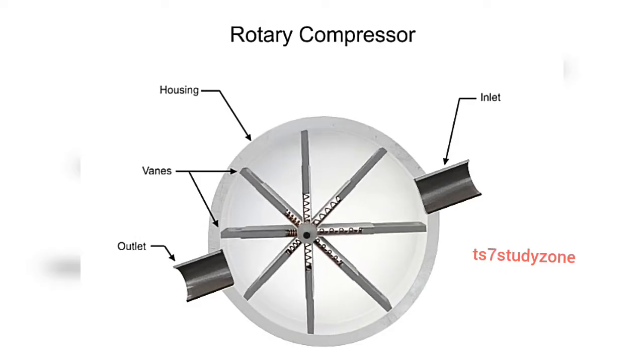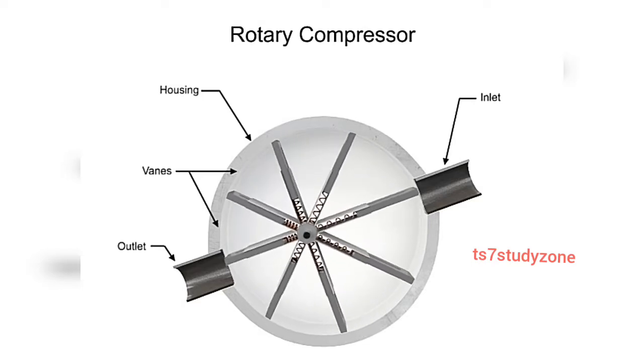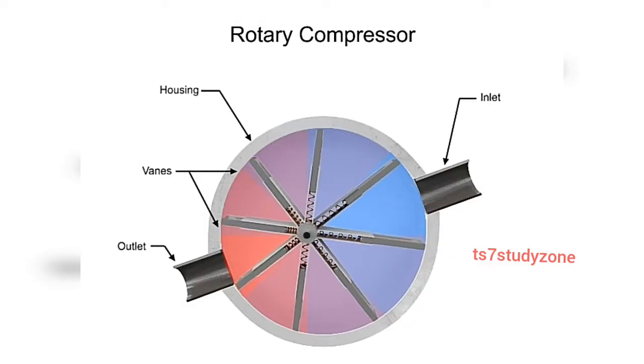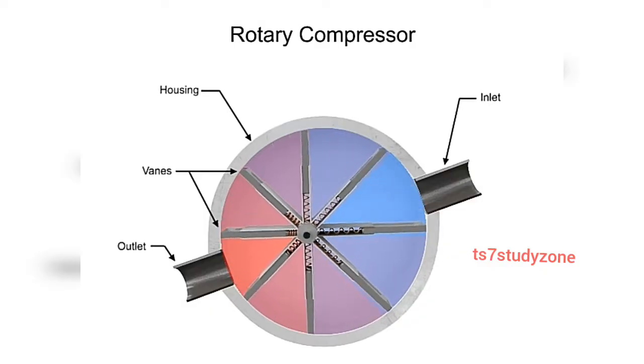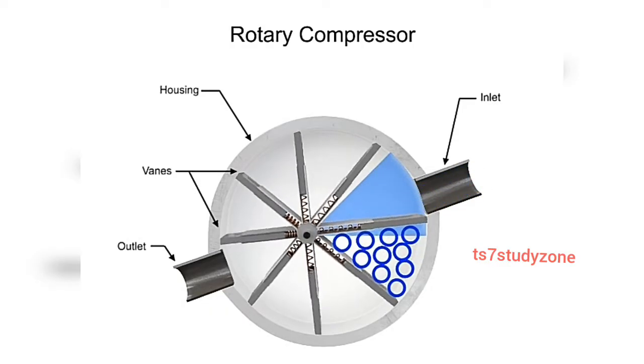As the shaft rotates, the vanes slide in and out to maintain contact with the cylindrical compressor wall. As they do, they create chambers within the cylinder of varying sizes. Air enters at the largest chamber.